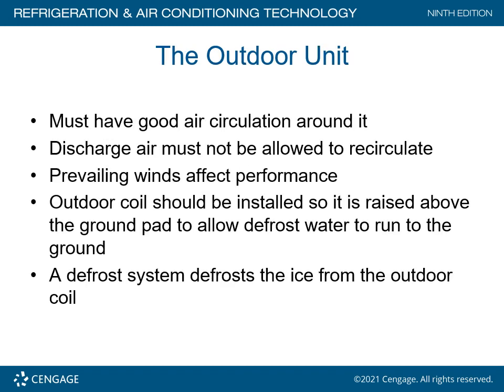The outdoor unit must have good air circulation around it. Discharge air must not be allowed to recirculate. Prevailing winds affect the performance. The outdoor coil should be installed raised above the ground pad to allow defrost water to run to the ground, okay? That's another reason why the unit needs to be off the ground, so that when the coil is defrosting, the moisture on the outdoor coil is going to run off and into the ground. And of course, we won't have an issue with water accumulating and possibly freezing up, depending on the outside air temperature. The defrost system defrosts the ice from the outdoor coil.